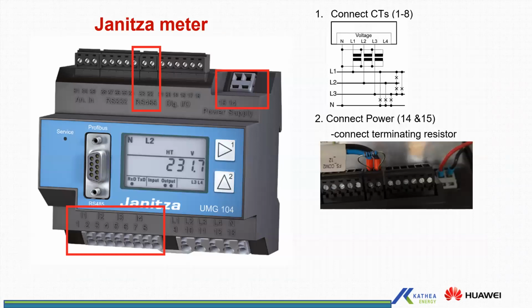And then for our meter connection for the C&I, mostly we distribute an Janitza meter, which is mainly the 104, the one with the screen, or the 103, the one without the screen. Whenever you're supplied with a meter, it's supplied with a 120 ohm resistor, which is basically an end of line termination resistor. You need to connect your line voltages, that is for reference L1, L2, L3, and neutral. And then you need to connect your CTs to the meter. The meter by default supports CTs with a secondary winding of 5A. However, they can also support CTs with a secondary winding of 1A, but preferably 5A secondary winding rating.